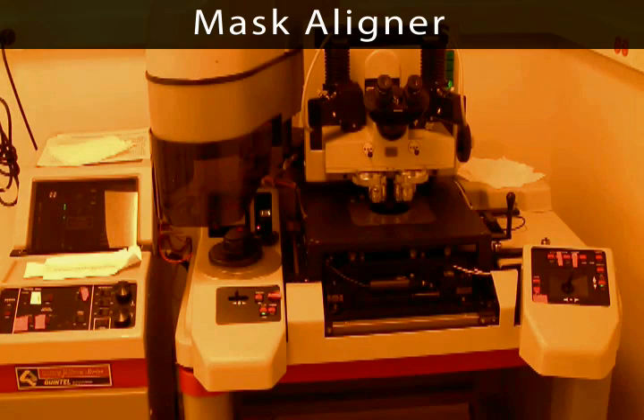Contact mask aligners are used in most microfabrication research laboratories. Nearly all microscale devices and structures require more than one photomask step. The contact aligner allows the user to align microscopic features already on a wafer with those on a photomask. Prior to using the mask aligner, the photomask is mounted onto a glass plate.